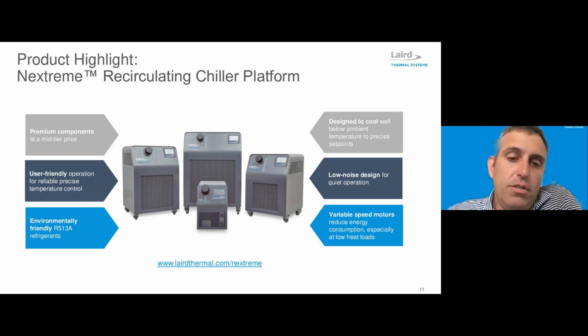The interaction with the system is through a touchscreen LCD display. So we recognize that users of the equipment in laboratories are not spending a lot of time with the chillers, and so we need to make that time as efficient as possible. With the touchscreen LCD, we're able to communicate directly with the user. So if there's an alarm on the system, we can display specifically with text what that alarm is, rather than displaying an alarm code that then needs to be looked up in the manual and we need to figure out what's going on. We can very quickly look at the system, understand how it's operating, and take action if necessary.